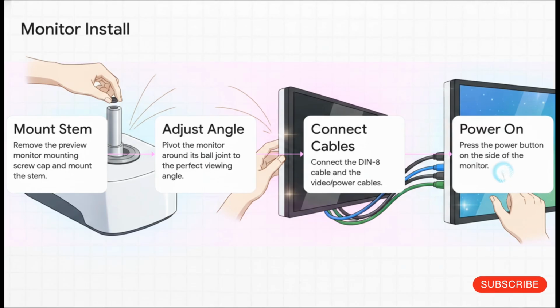First, you just remove the preview monitor mounting screw cap that's located right next to the status panel on top of the instrument and align the monitor stem's mounting screw directly into that hole. Second, you just use the adjustment knob on the stem to pivot the monitor around its ball joint until you've got the perfect viewing angle. Third, connect the supplied DIN 8 cable and the video cables. And finally, just hit the power button on the side of the monitor.